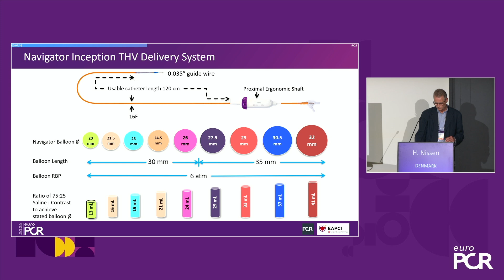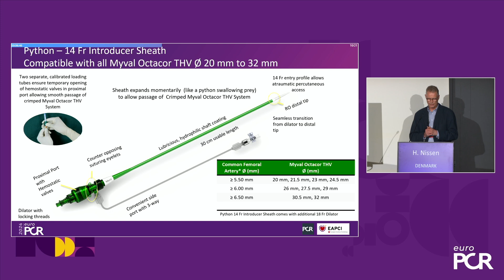Okay. They have their own proprietary sheath, which is expandable. Same sheath used for all sizes. It comes with a loader for 2 different loaders depending on the valve size, but it's the same valve that goes into the same sheath, regardless if you start with the 20 or you end with the 32, and it works quite nice. For the larger valves, it's recommended that we do a pre-dilatation with an 18 French dilator before you introduce the valve.